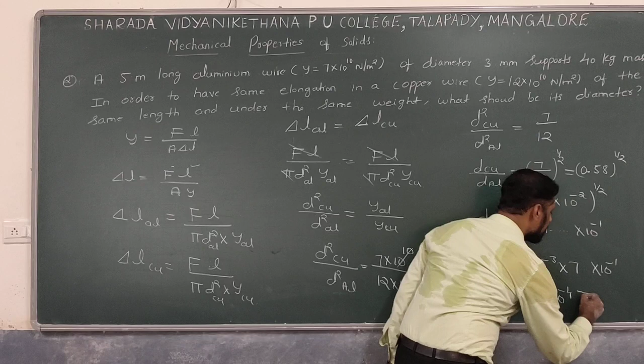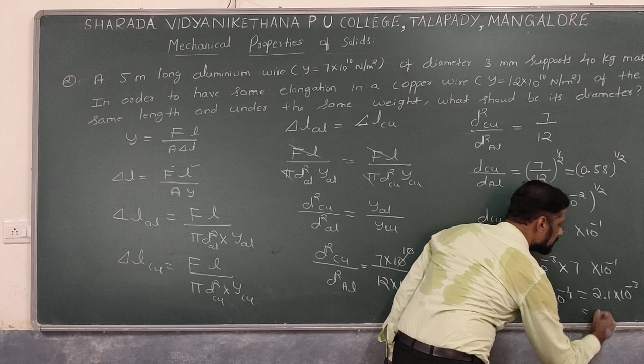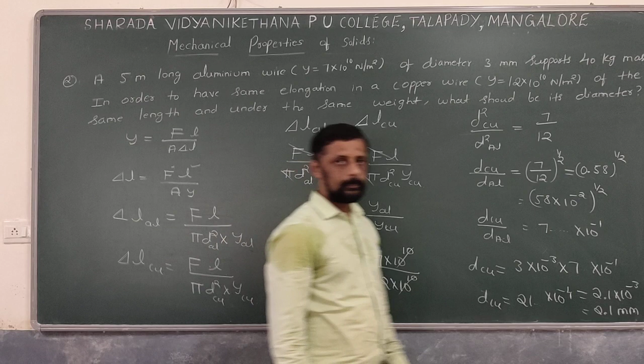So therefore diameter of the copper wire is equal to, take this term to RHS, it goes to the numerator. Diameter of the aluminum wire is how much? 3 mm. That means 3 into 10 power minus 3 into 7 point something into 10 power minus 1. So diameter of the copper wire is equal to 21 point something into 10 power minus 4. That can be written as 2.1 into 10 power minus 3 meter. That is nothing but 2.1 millimeter, which is the diameter of the copper wire.